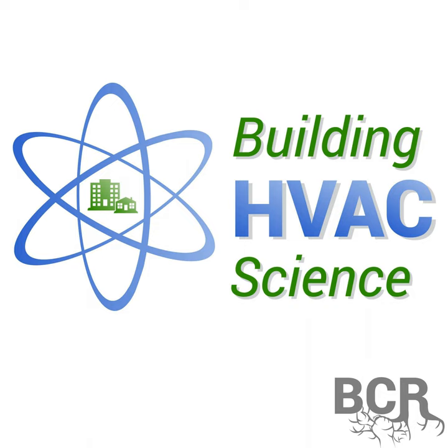So now, instead of fighting with the forced air crowd to say we do it better, we're more comfortable, we think the best delivered product is going to be a hybrid system where you have a forced air component that can be downsized so you're not doing two redundant systems. Traditionally, we go with the DOAS, a dedicated outdoor air system, combined with radiant cooling, and it's the perfect match for us. So we can still keep the humidity levels in check, bring in fresh air, but then drive most of the sensible loads with the radiant floors. So then you have a nice cool surface in the summer instead of just turning down the temperature of the air that you're blowing around.